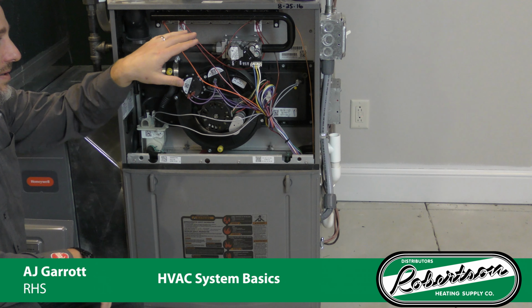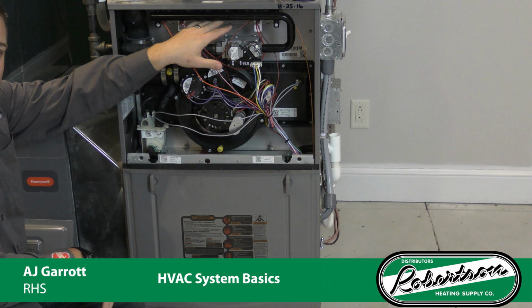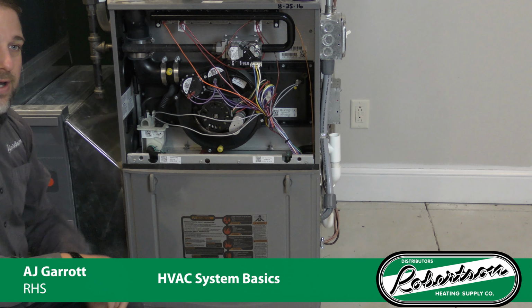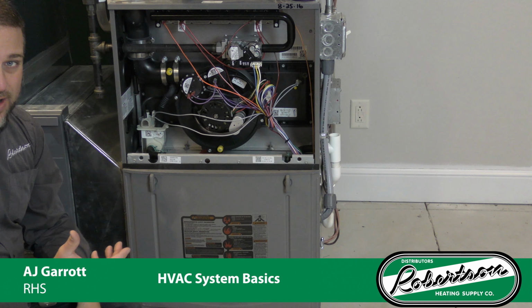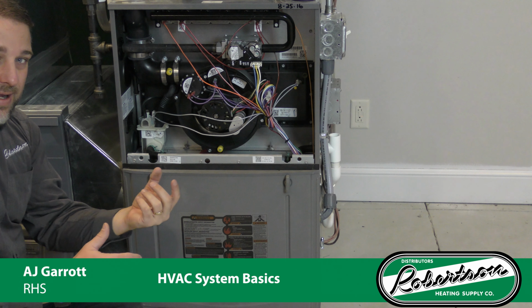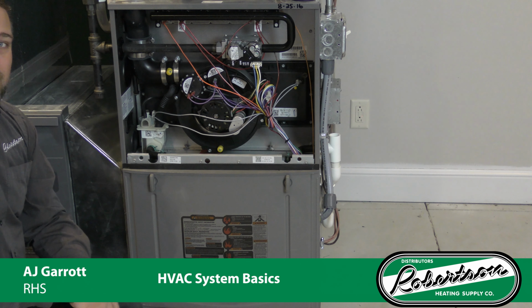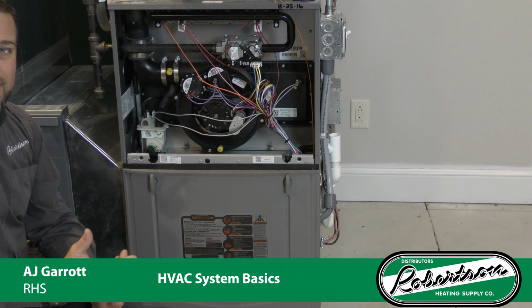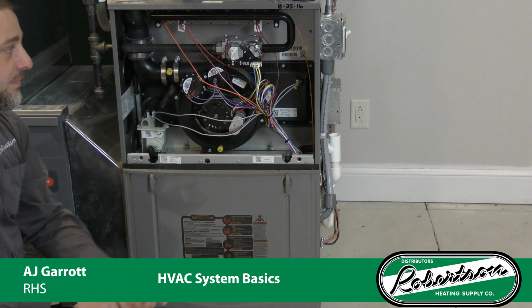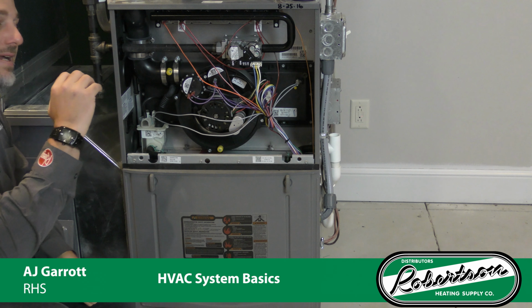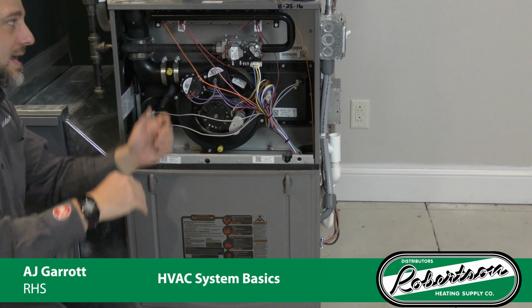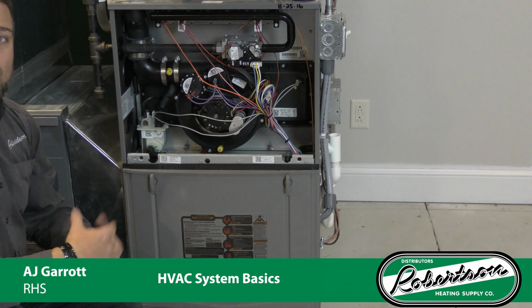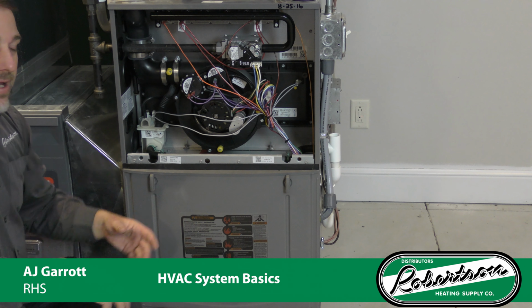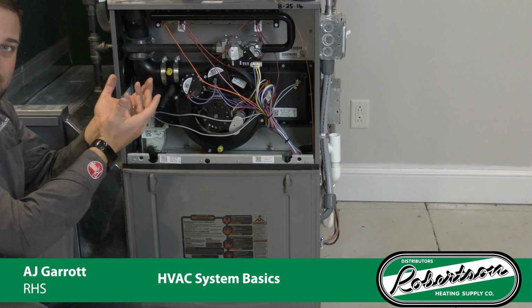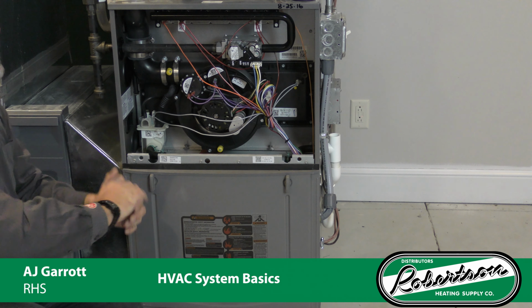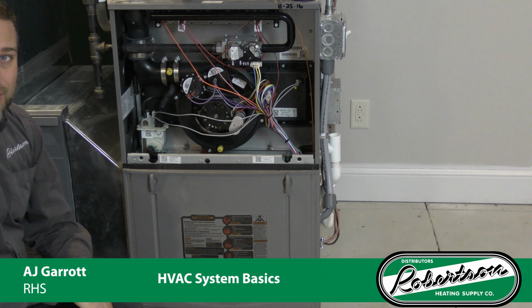When the gas comes out of the orifices and through the burners, we have an igniter over here. It can either be a hot surface igniter, which glows very hot and red, or it could be a direct spark igniter, which sparks kind of like a gas stove or a gas grill. So it lights the gas, and the gas then shoots a flame into the heat exchanger, warms up the heat exchanger, and then as air passes over that heat exchanger, it warms the air and sends it into the rest of the house.